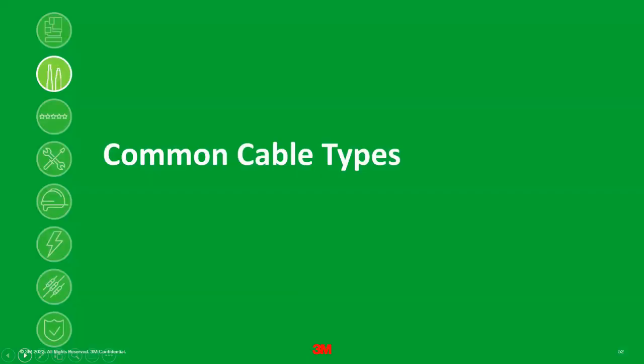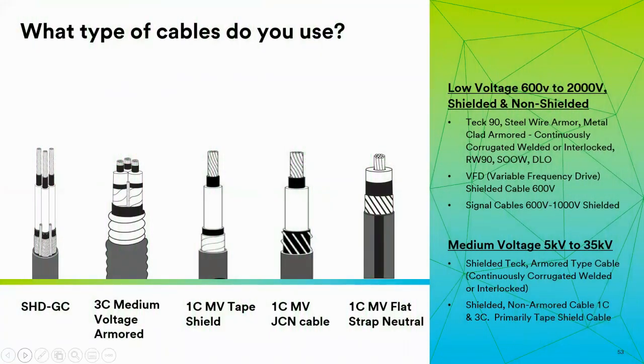So now I'll talk about the most common types of medium voltage cable. From this page, the three most common cable types I see are the second one there, the 3-conductor medium voltage armored cable, most commonly found in industrial settings. The tape shield cable, so that's the copper tape shield. And then the fourth one there would be the jacketed concentric neutral cable. The JCN cable is a lot of the utility distribution; also wind and solar farms will be using the jacketed concentric neutral type cables.